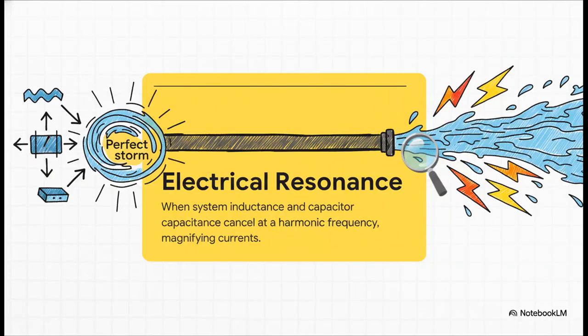And that is what sets the stage for something called resonance. This is the absolute perfect storm. At one very specific harmonic frequency, the rising impedance of the system can perfectly match the falling impedance of the capacitor. They cancel each other out, creating an almost zero impedance path. It's like you've just opened a fire hose for all those nasty harmonic currents.